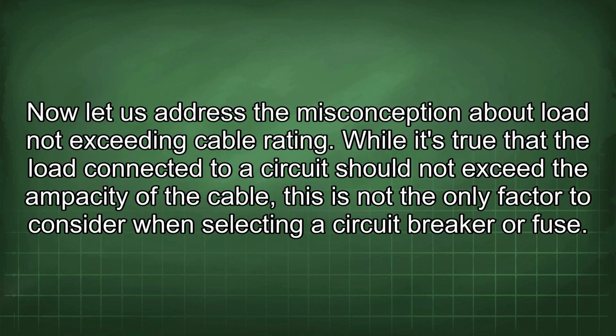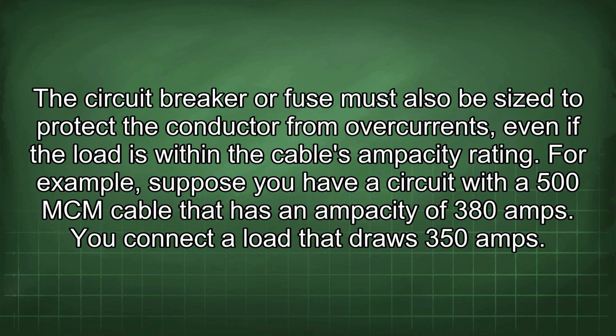Now let us address the misconception about load not exceeding cable rating. While it's true that the load connected to a circuit should not exceed the ampacity of the cable, this is not the only factor to consider when selecting a circuit breaker or fuse. The circuit breaker or fuse must also be sized to protect the conductor from overcurrents, even if the load is within the cable's ampacity rating. For example, suppose you have a circuit with a 500 mcm cable that has an ampacity of 380 amps. You connect a load that draws 350 amps.